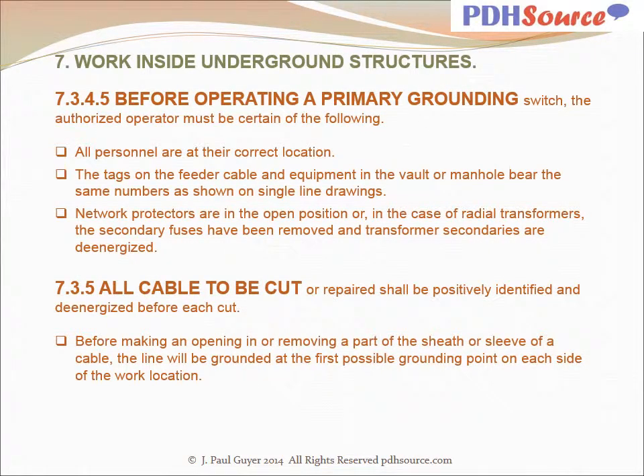Before operating a primary grounding switch, the authorized operator must be certain of the following. All personnel are at their correct location. The tags on the feeder cable and equipment in the vault or manhole bear the same numbers as shown on single-line drawings. Network protectors are in the open position, or in the case of radial transformers, the secondary fuses have been removed and transformer secondaries are de-energized. All cable to be cut or repaired shall be positively identified and de-energized before each cut. Before making an opening in or removing a part of the sheath or sleeve of a cable, the line will be grounded at the first possible grounding point on each side of the work location.